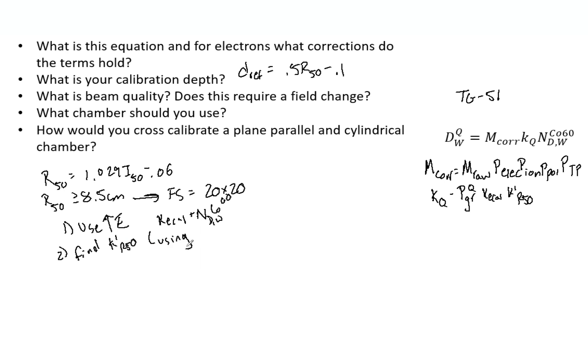That is just going to do using R-50. And then next, we want to cross-calibrate at D-ref using a cylindrical chamber. The calibration is equal to the dose measured with the cylindrical chamber divided by the plane parallel chamber's reading times K-prime R-50.